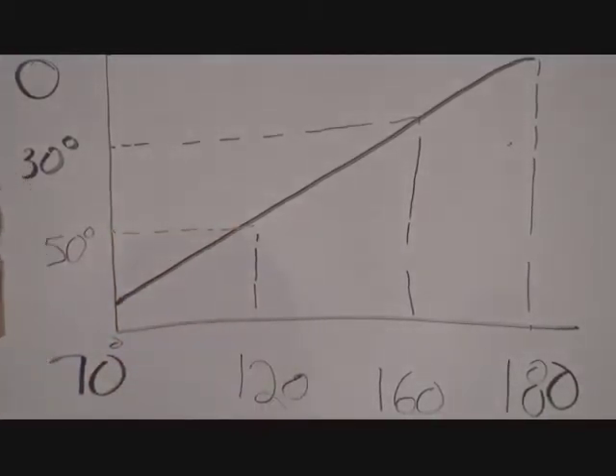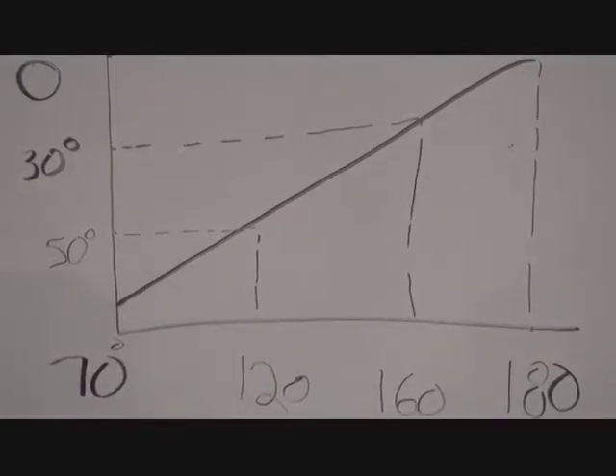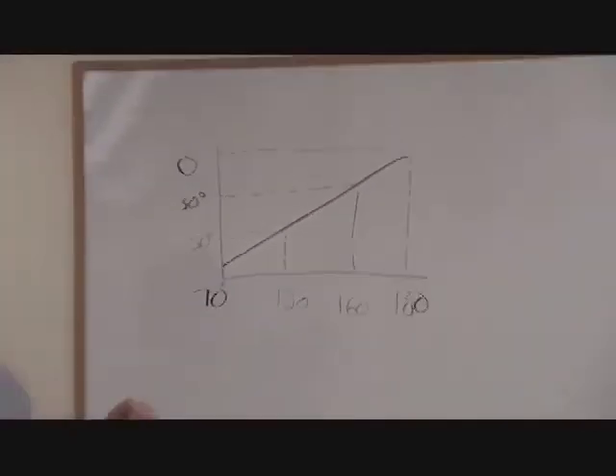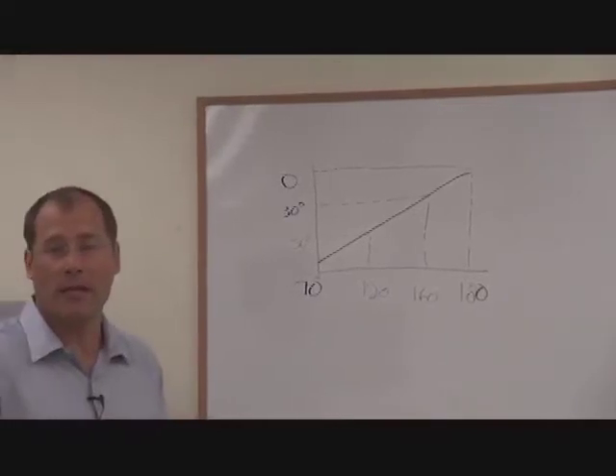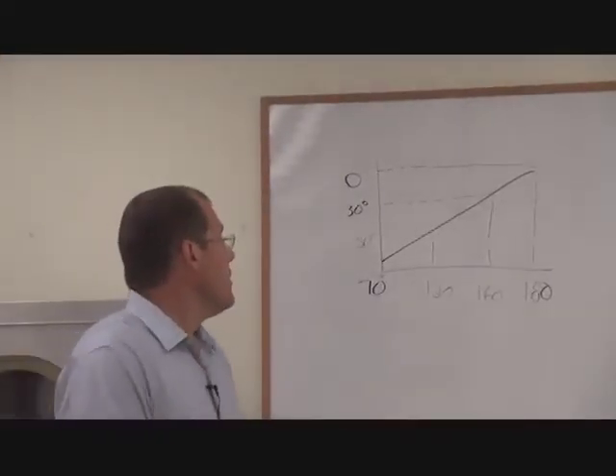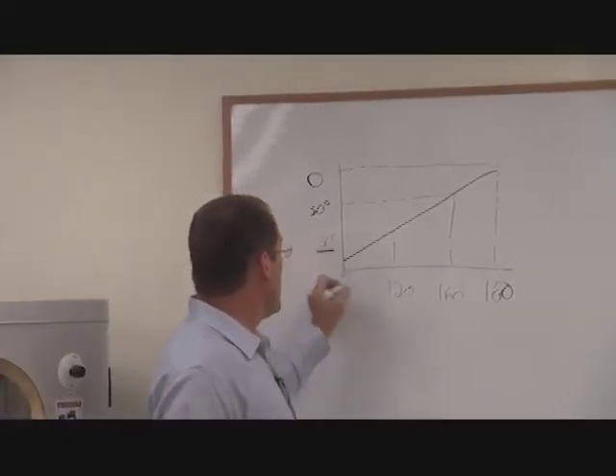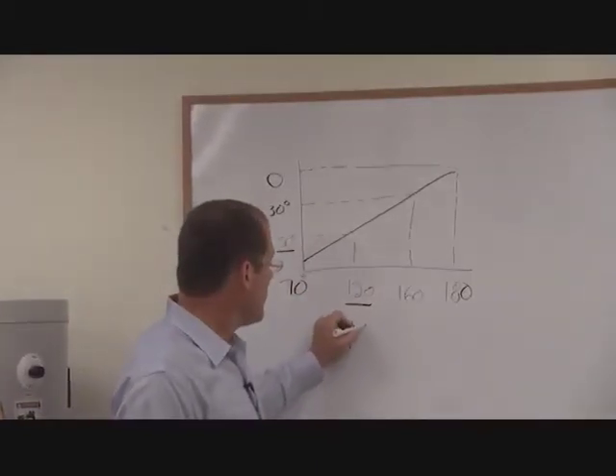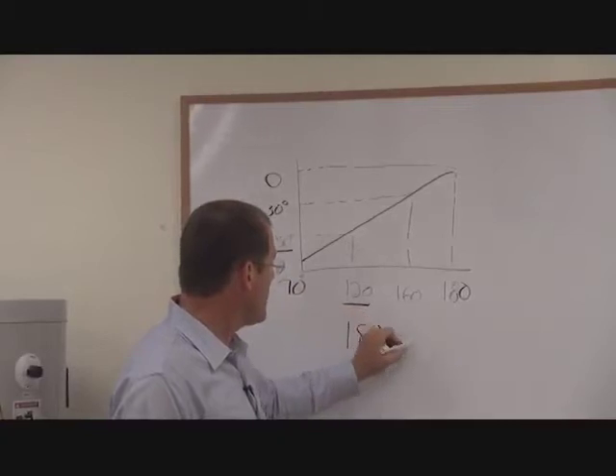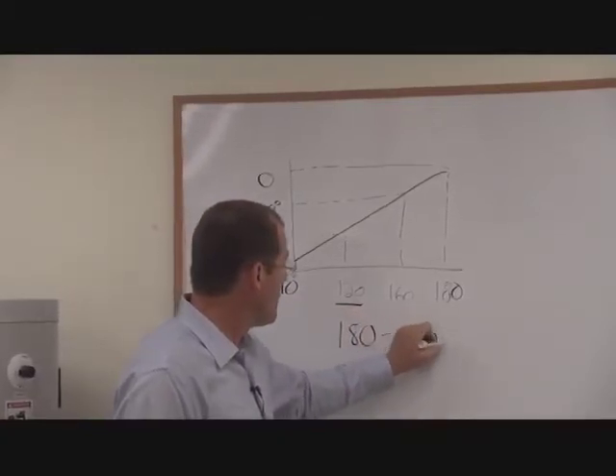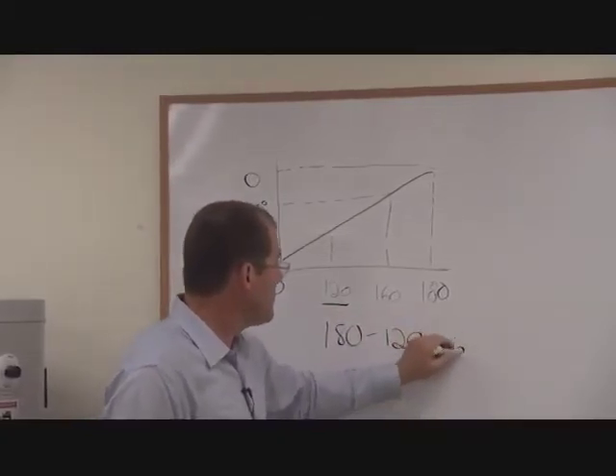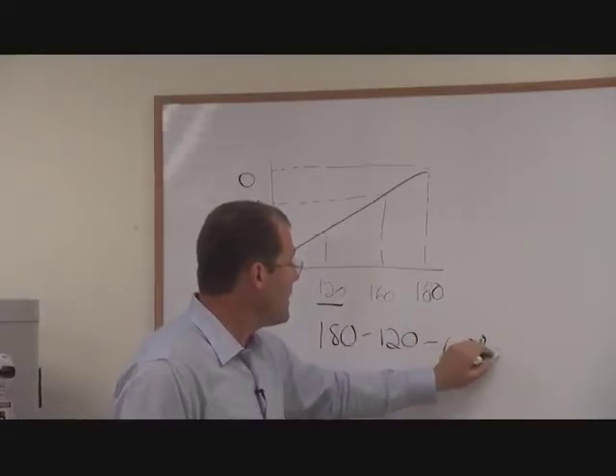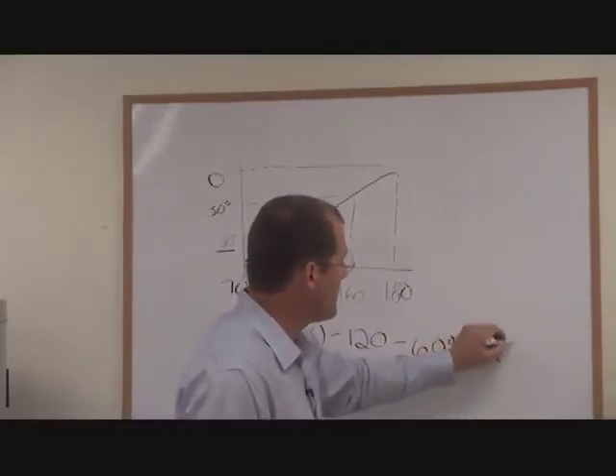Now where this efficiency comes in is every three degrees that you can lower the boiler's water temperature you gain a percent in operating efficiency. So if on this milder day we can be at 120 degrees, we have saved 60 degrees of temperature and that equals 20 percent operating efficiency gain.